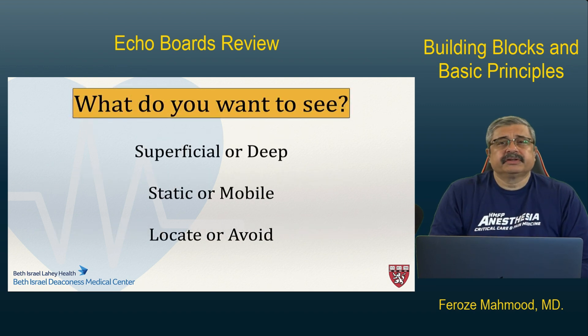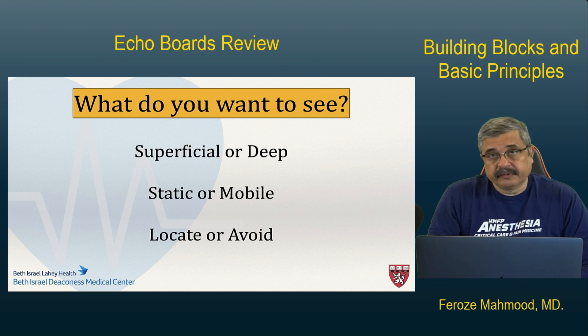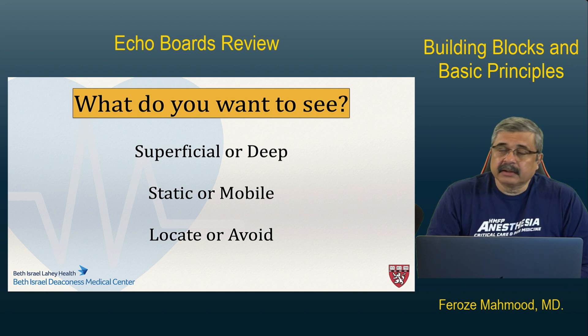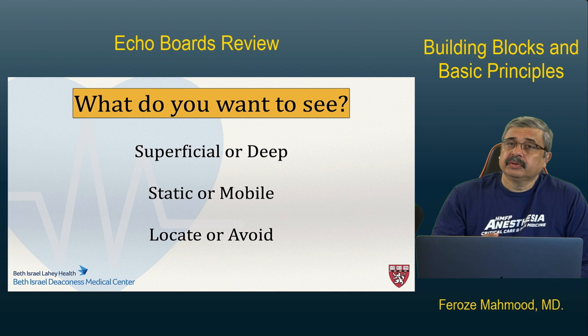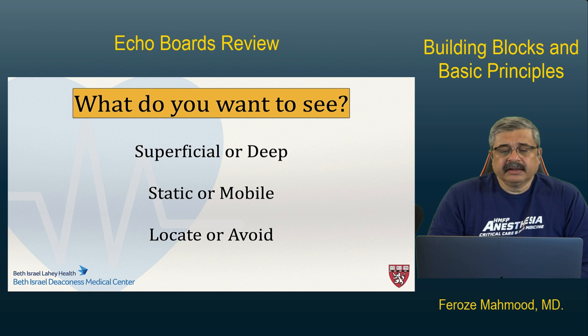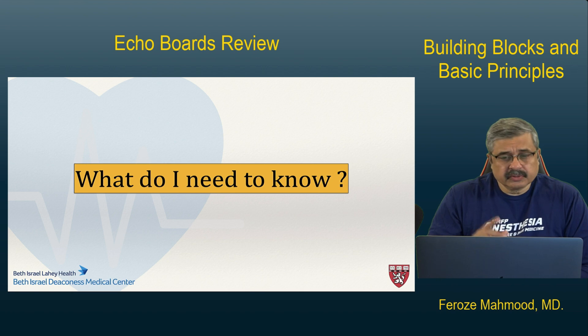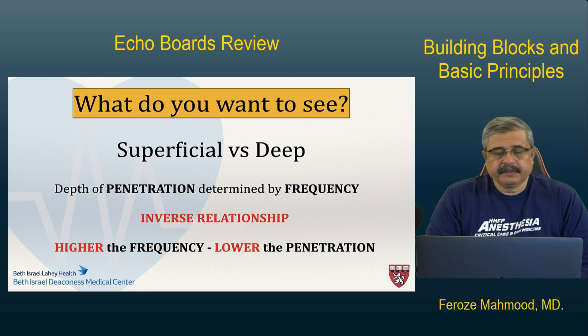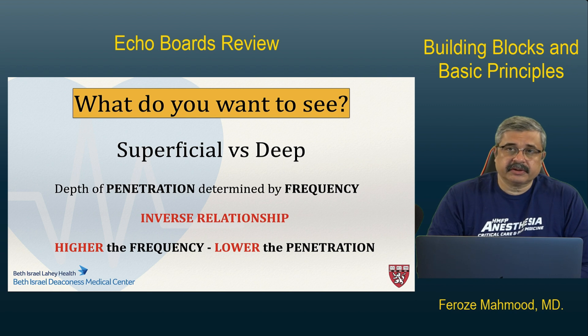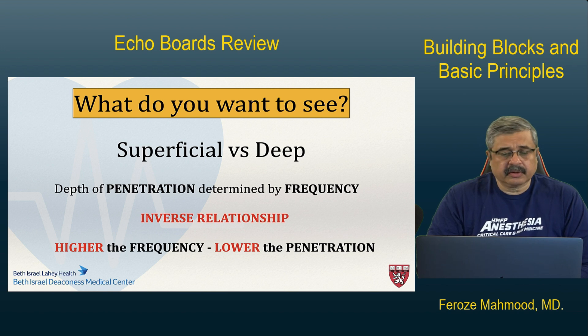When selecting what you want to see, the next question is whether it's a superficial structure or deeper in the tissues. Is it static or mobile? Do we want to optimize the image, or avoid a certain structure? These questions need to be answered before starting a clinical examination. Superficial versus deep matters because depth of penetration is determined by frequency, so transducer choice is the first decision to make.